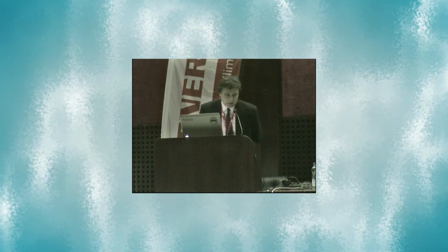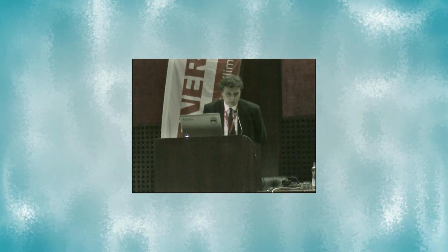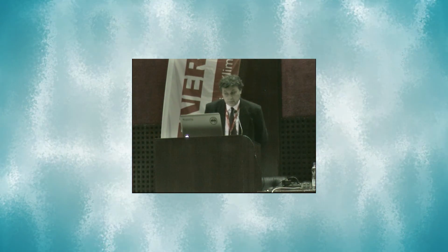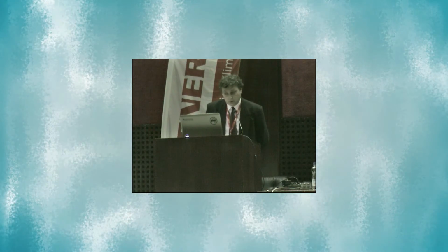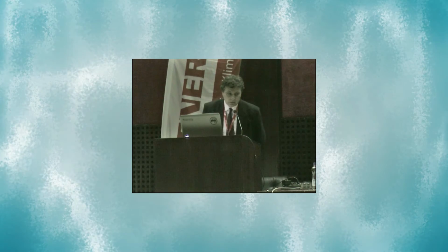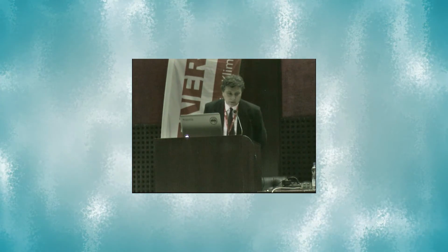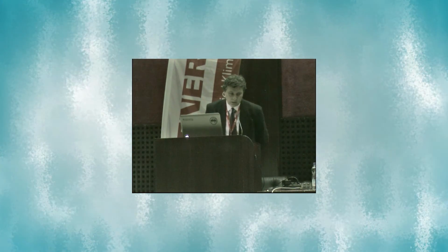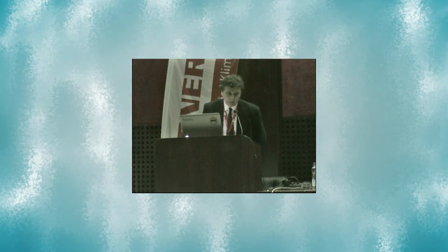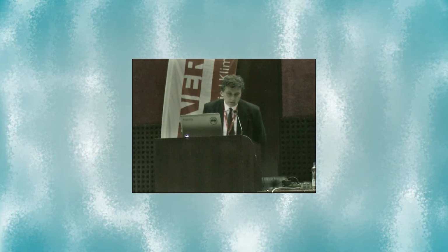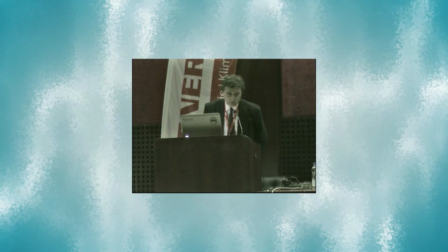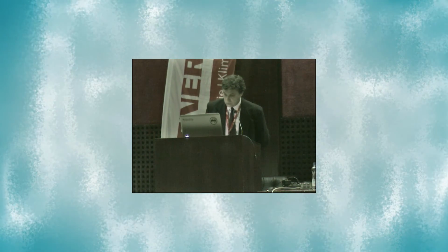This project is a typical example of design and commissioning deficiencies, which we identified through an energy audit, and surprisingly we identified the opportunity to save in excess of 50%, I mean to reduce energy consumption of the HVAC system by the order of 50%. Main deficiencies related to the envelope of the building and controls. So in terms of envelope, I will show you next one.